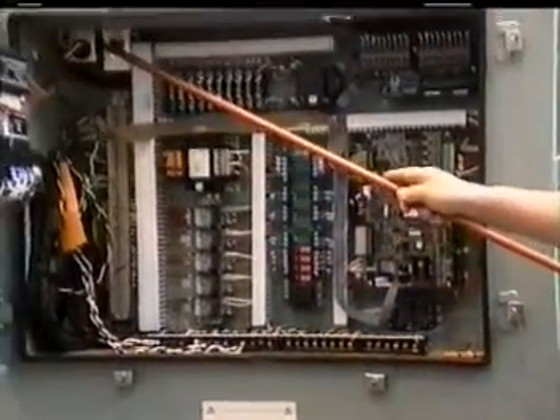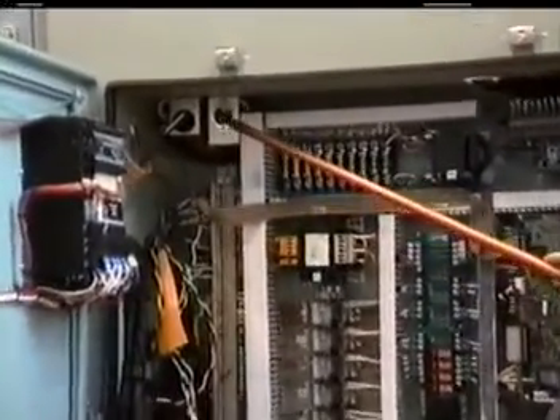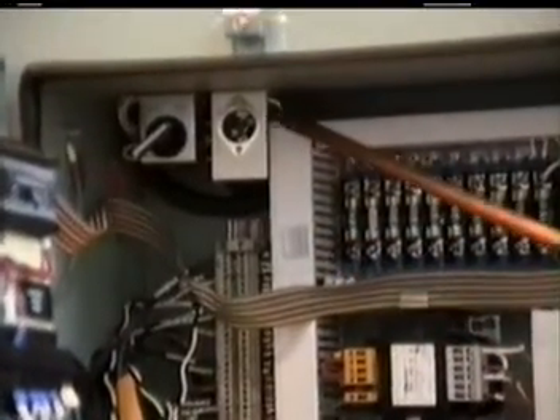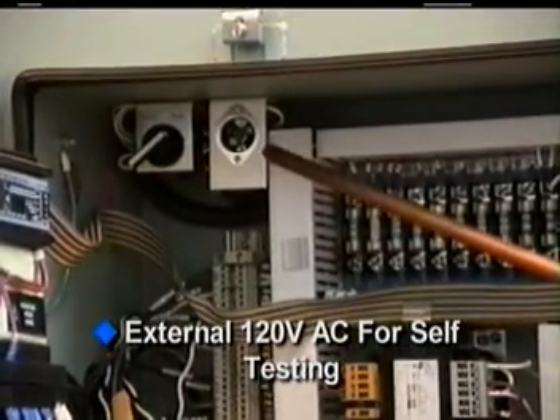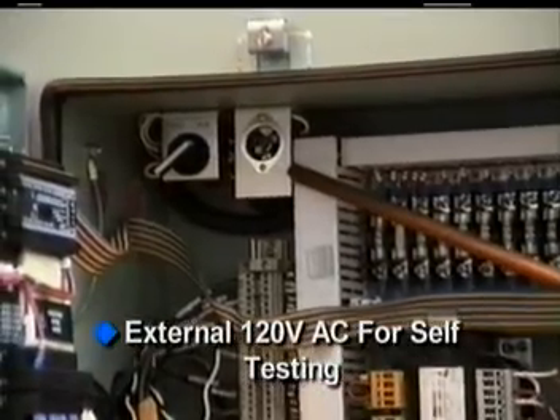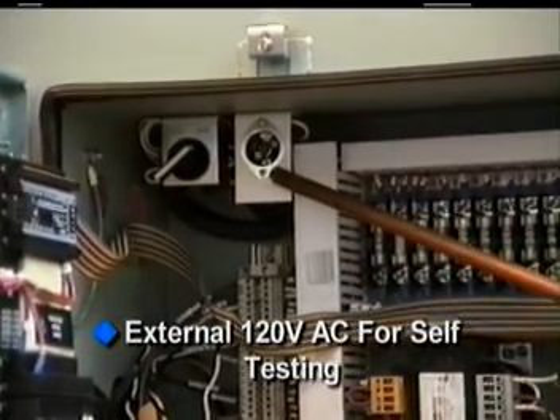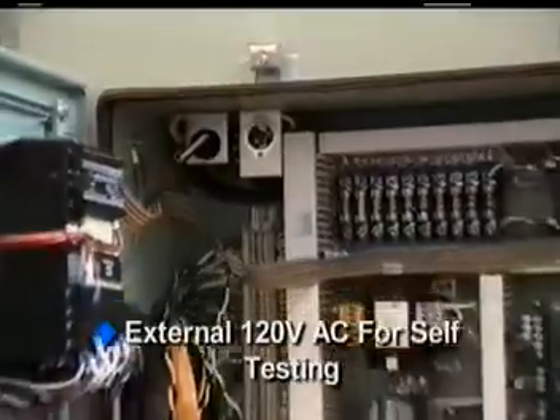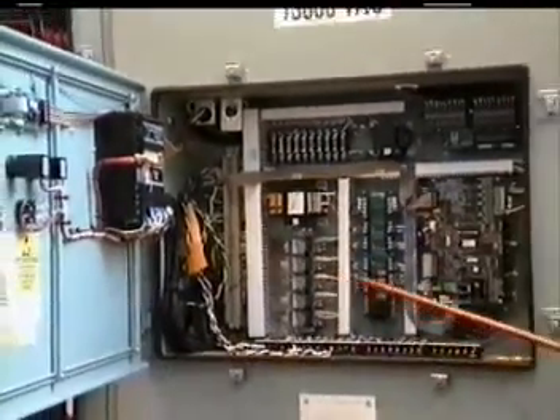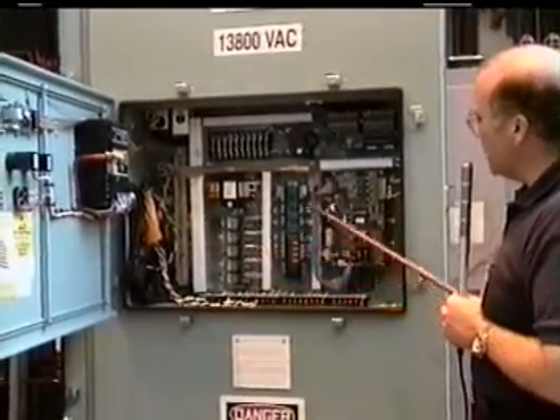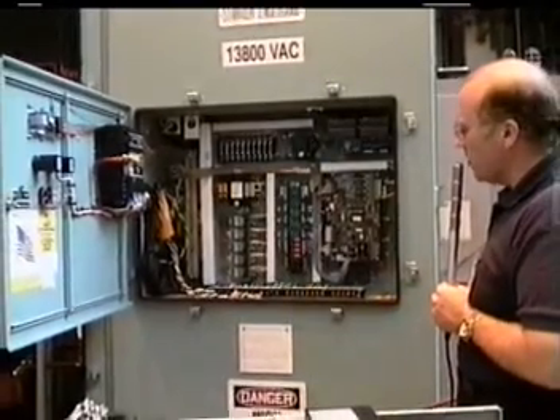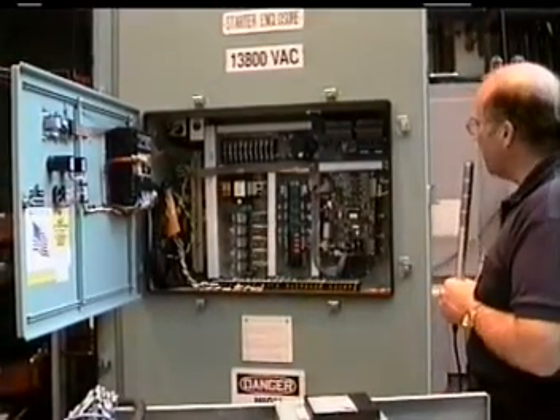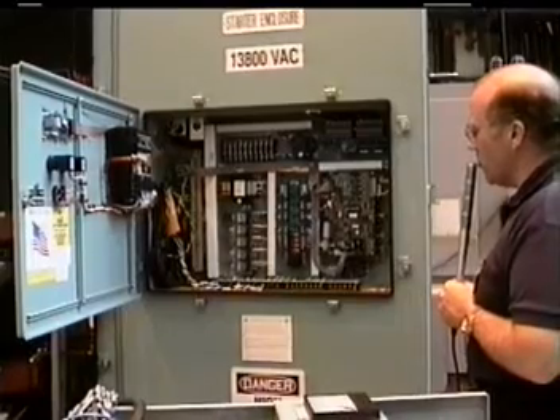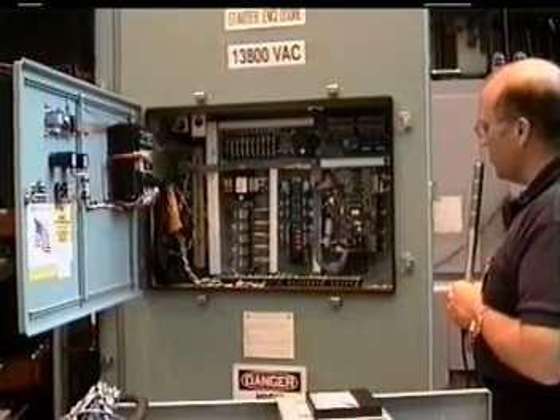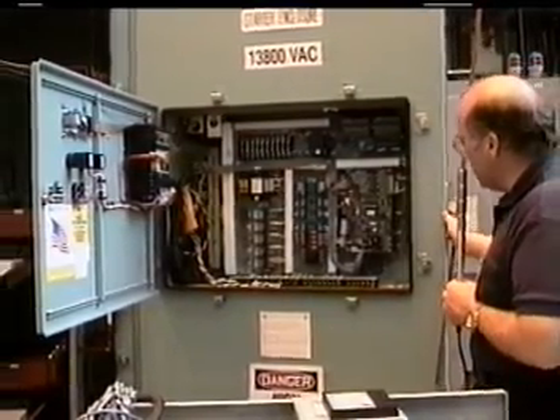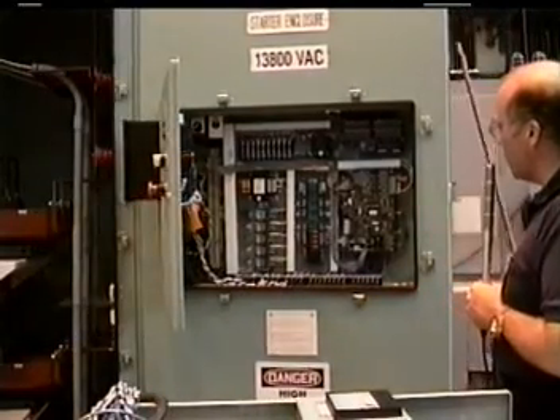In this section over here we have a test and a run switch, which allows for the operation of the starter in test mode by bringing in an external 120 volts power to the test plug here. In this operation mode you can provide for low voltage testing to prove that the microprocessor electronics as well as the contactors are operational. You can also verify SCR gate pulses within the solid state stacks, which are behind this door here in the starter enclosure section.